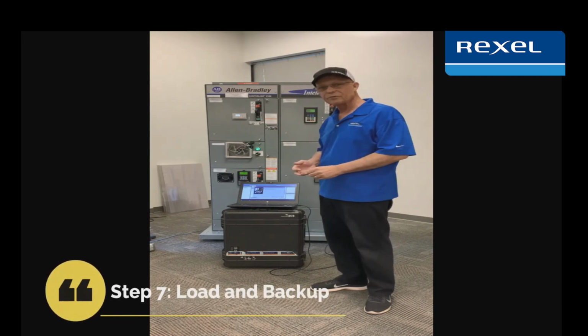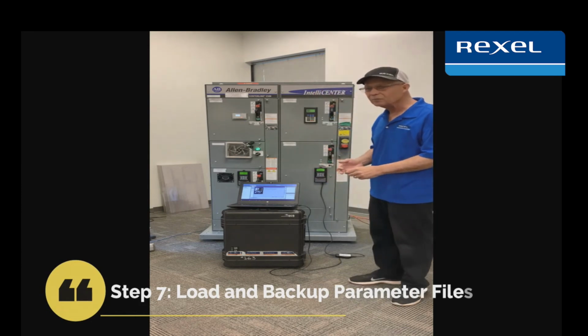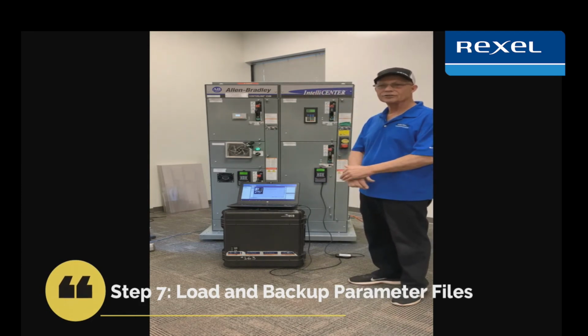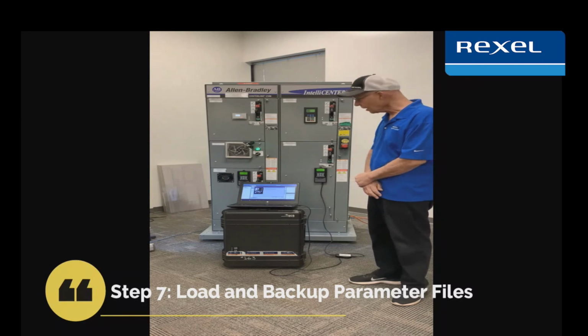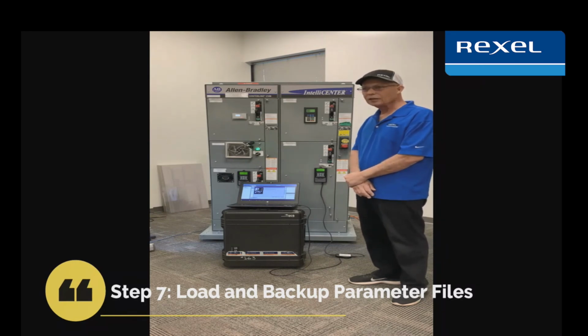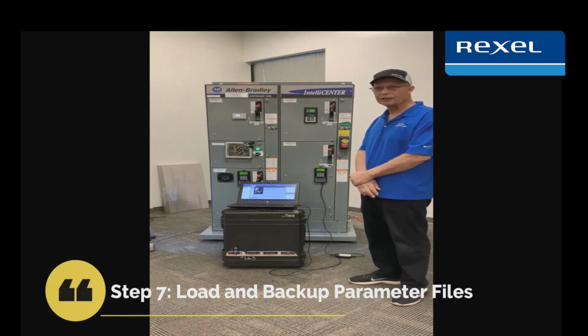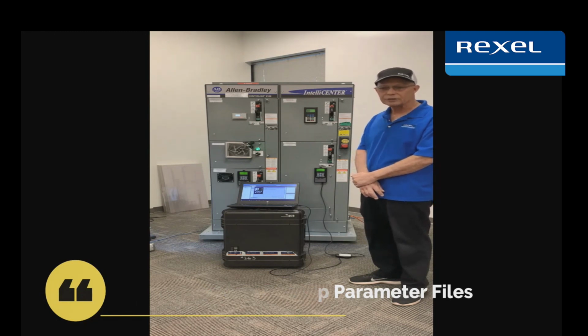with results obviously all being good, I'll save the drive file to the HIM. In the event that the drive is lost or something happens, they can download that file into the new drive, saving a tremendous amount of time. They won't have to go back and reconfigure anything. I also will upload what we call a technical wizard file. It basically covers all the parameters that were changed, errors, everything into a file that Rockwell Automation would need in regards to the customer ever calling in tech support on this drive. And it could benefit me too as far as being a service technician.